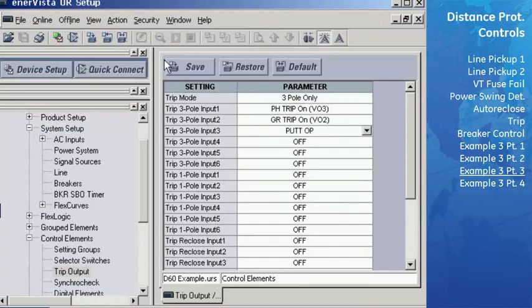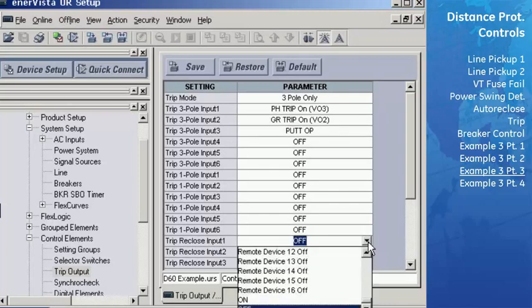The line pickup output is pre-configured inside the trip output scheme and does not need to be selected here. Since we are never tripping just one phase of the breaker, no trip 1-pole inputs need to be set. For our example, we only want to reclose upon faults that trip instantaneously and may be transient in nature. Therefore, we only want to reclose after the operation of a phase or ground distance zone 1 trip or a PUTT scheme operation. Therefore, select the Trip Reclose Input 1 as Phase Distance Zone 1 Operate.